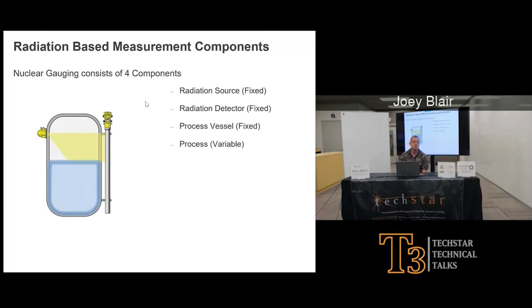Cobalt-60 is, to put it simply, has more penetration power. So if we have really thick walled reactors, sometimes our application engineers might choose cobalt-60, but typically you are going to see cesium-137. So that's our source side. Then on the other side, we have a radiation detector. Okay, for continuous level, as you see in this picture, you can see it's going throughout the entire measurement span.